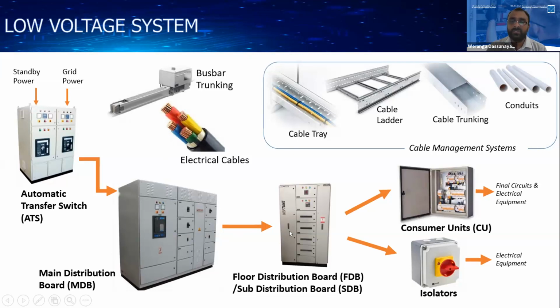Mostly after the main distribution board, the power is distributed using cables. To support those cables, you can use cable trays, cable ladders, or cable trunking. So finally, when this power comes to the final circuit, you may all have seen the cables are routed through conduit. So this is how the cables are managed throughout the building or premises. The importance of identifying these kinds of cable management systems is that, based on the cable management system, the current carrying capacity of the cable varies.